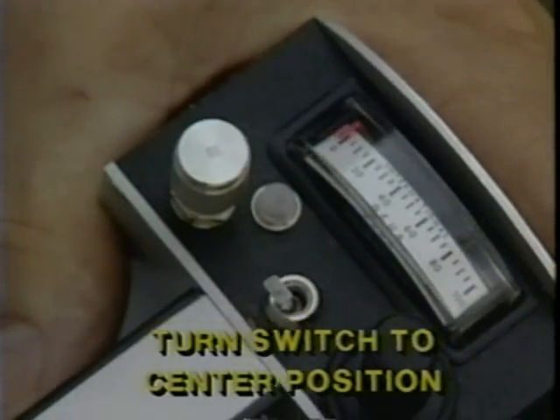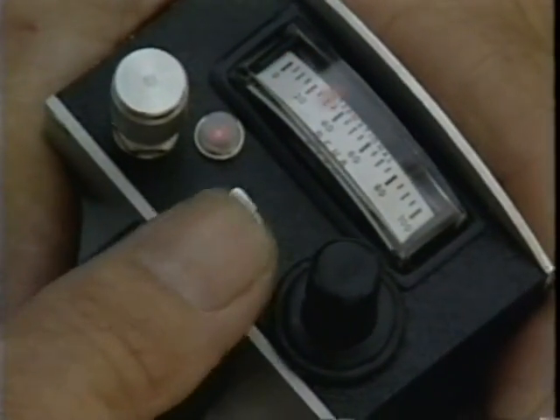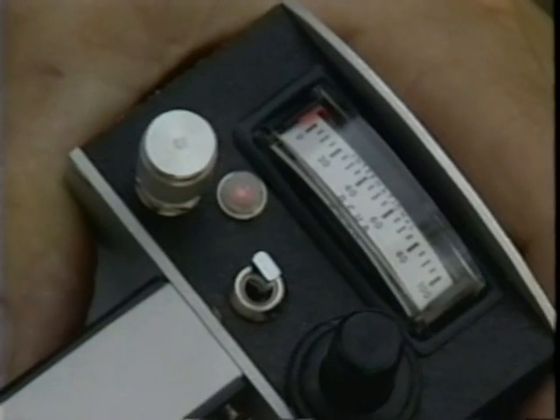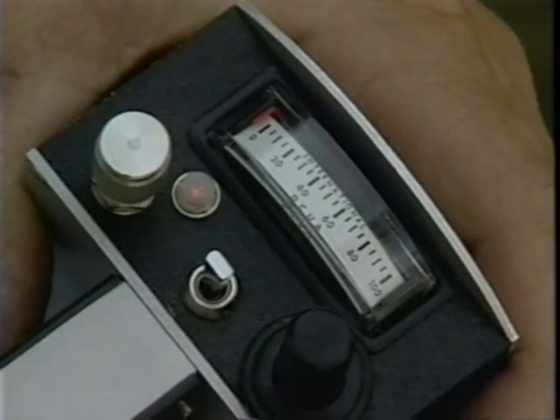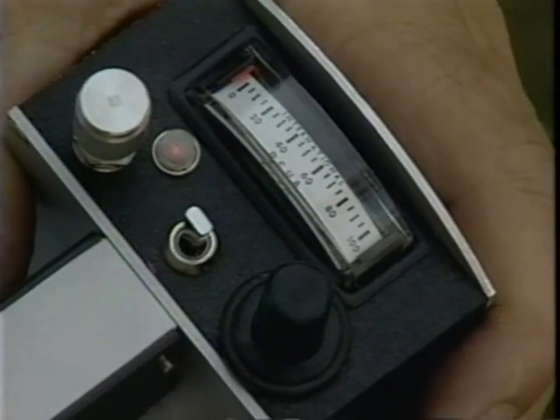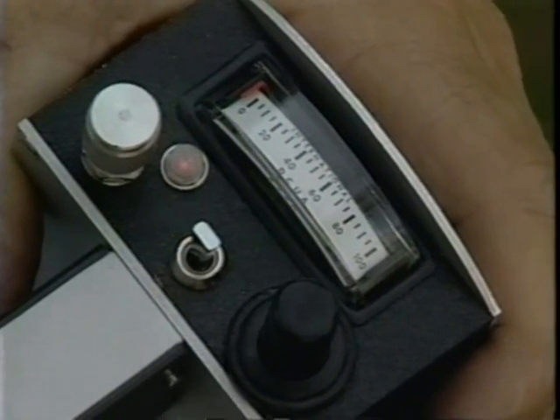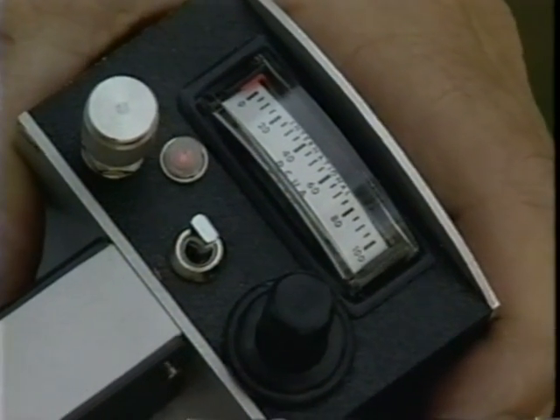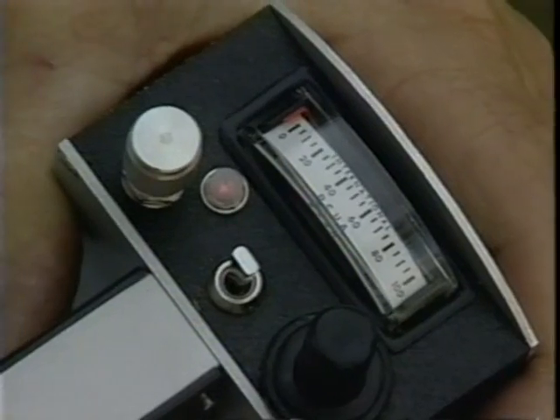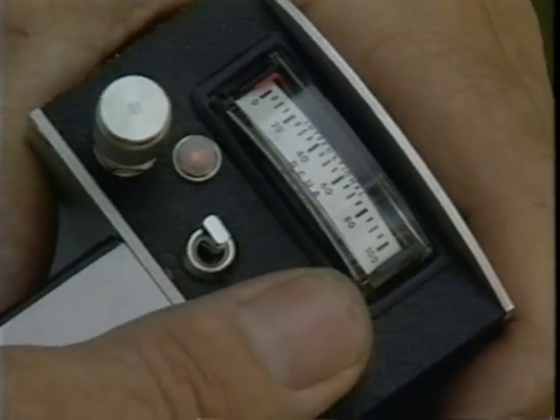Turn the switch to the center or on search position. The audible alarm should sound and the visual indicator light should come on, which indicates the flame is not lit. This is known as the flame out condition. If either the light or audible alarm do not work, the FlamePack 400 must be serviced.